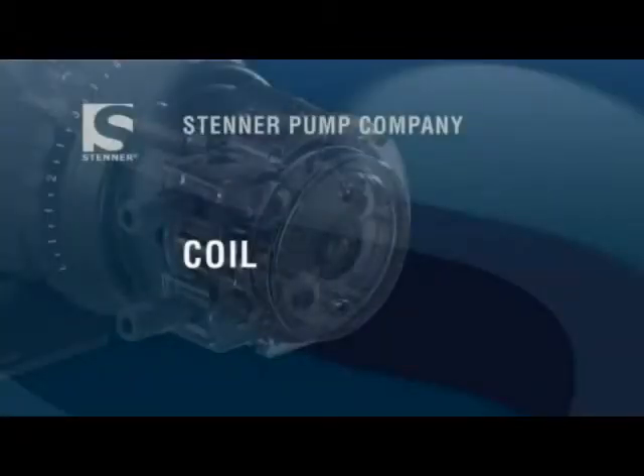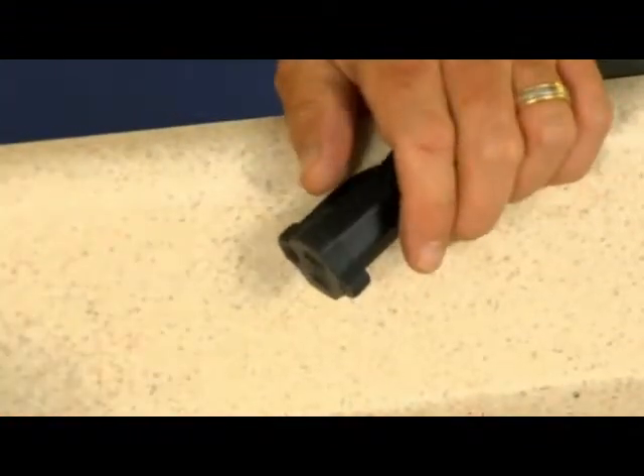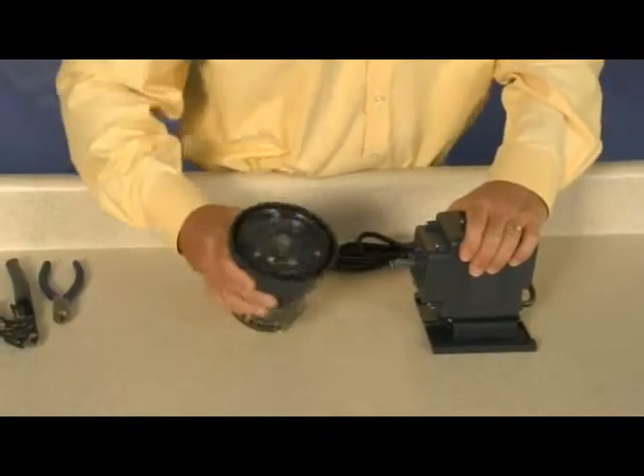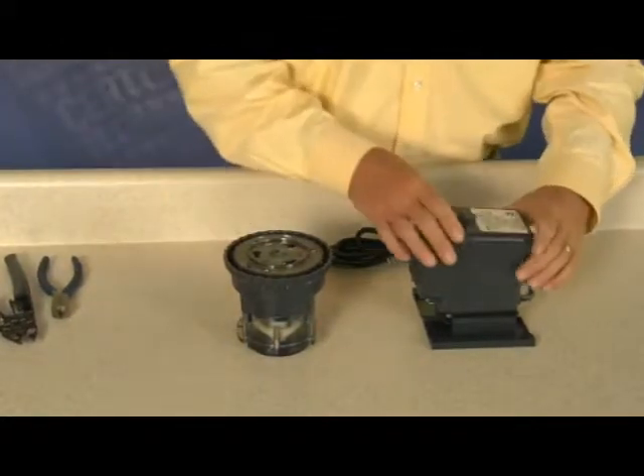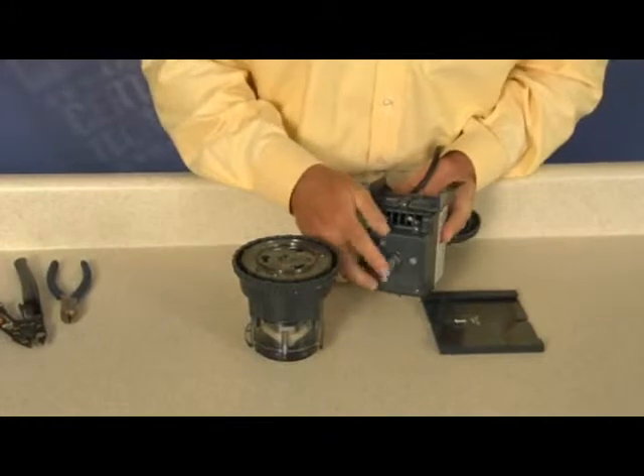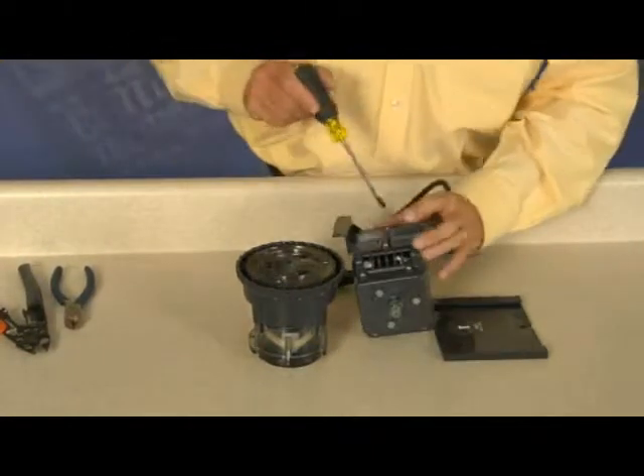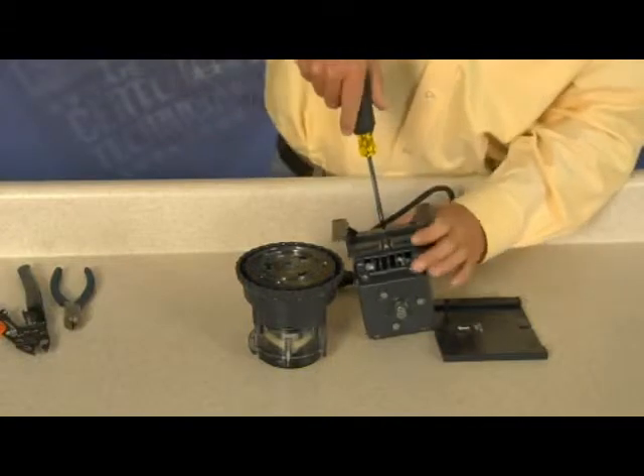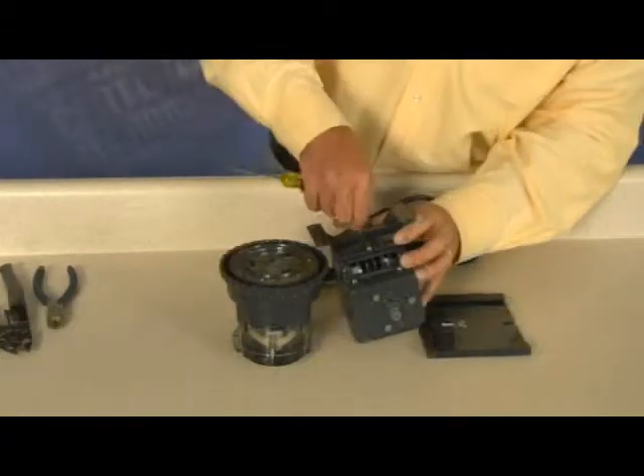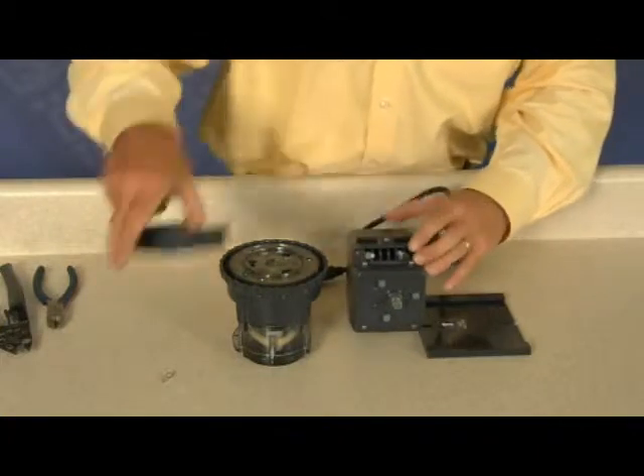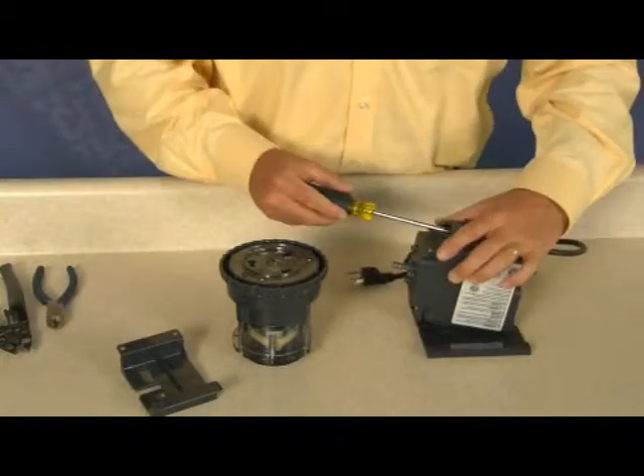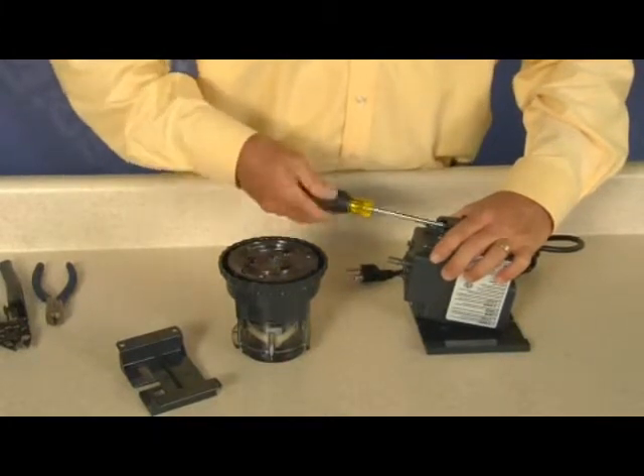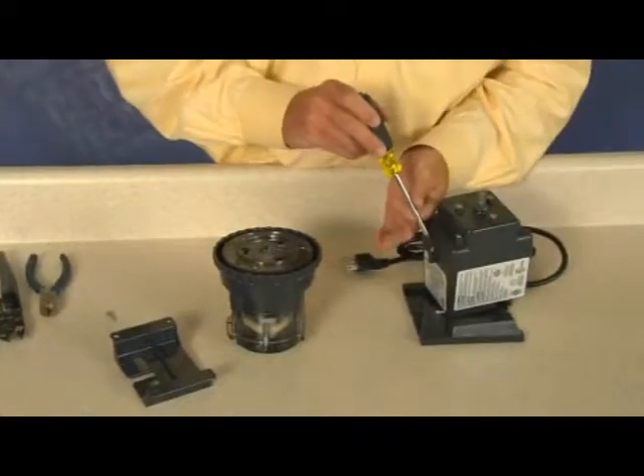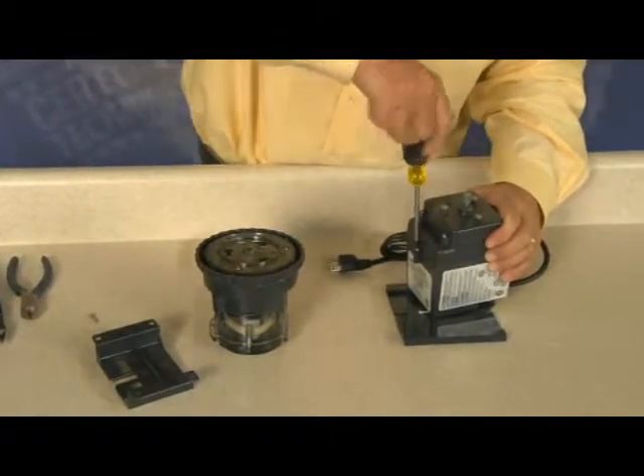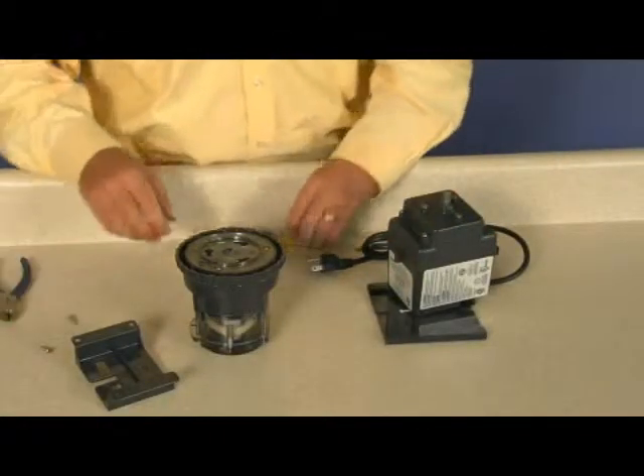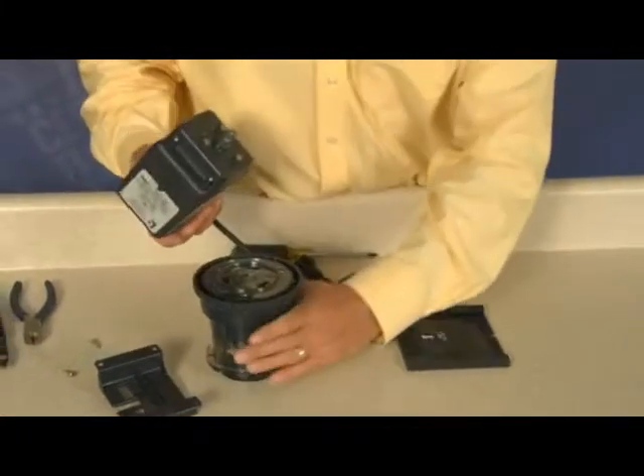To replace the coil, disconnect power to the pump. Separate the feed rate control and pump head from the motor. Remove and set aside the motor base. Remove 2 motor cover screws. Invert the pump and use the pump head and feed rate control as a stand to work on the motor.